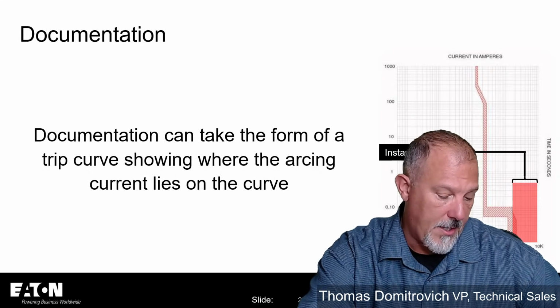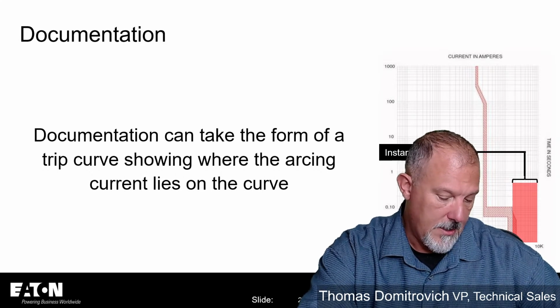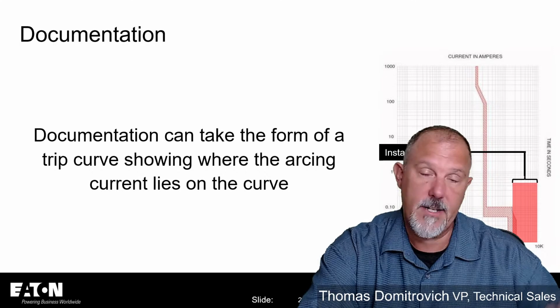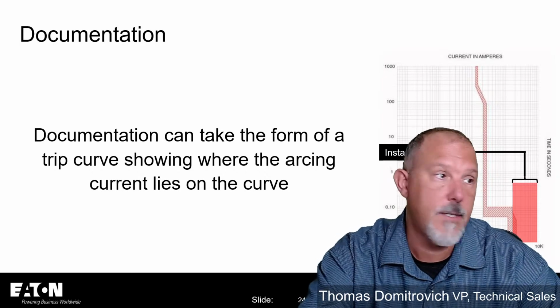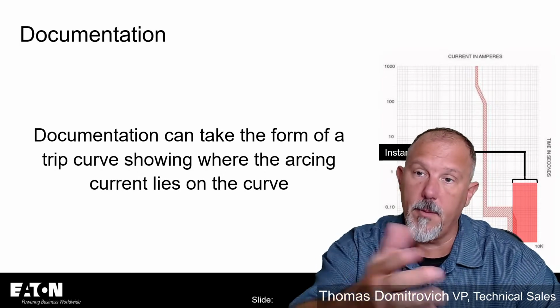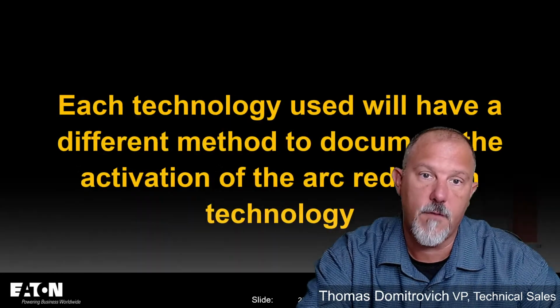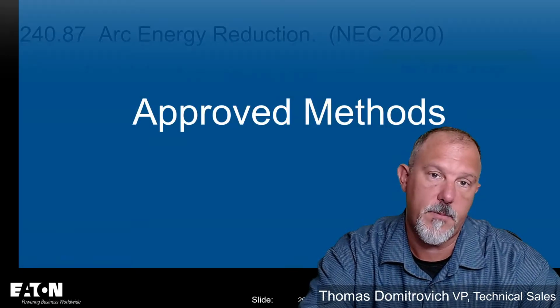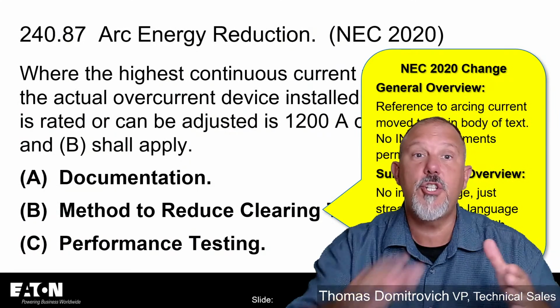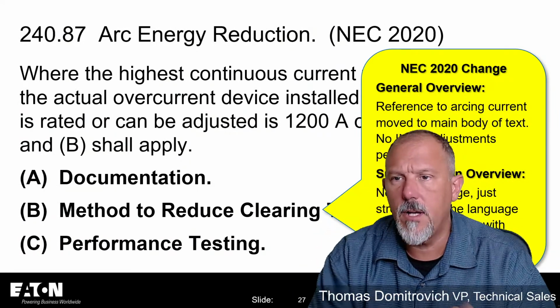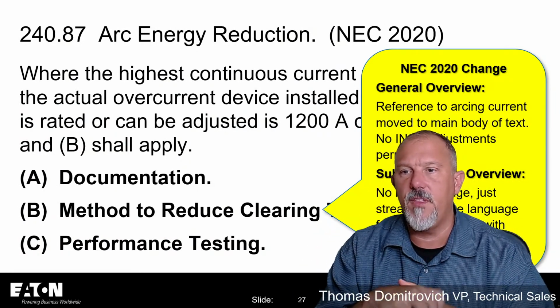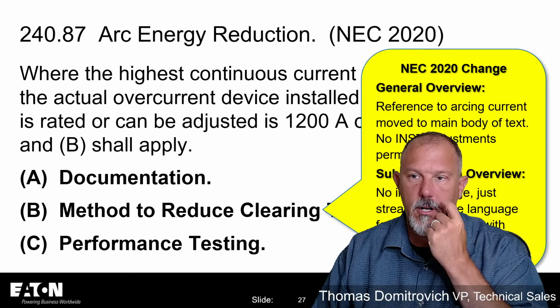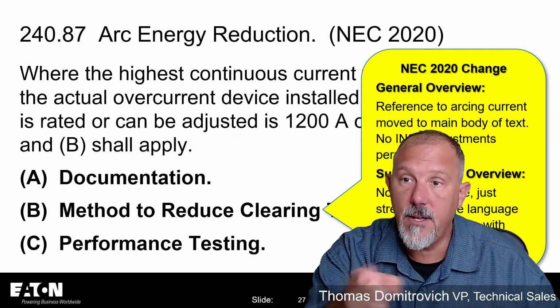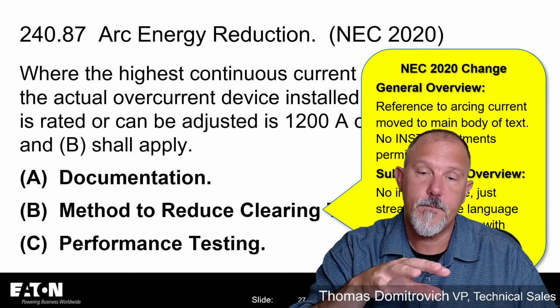But there's nothing in here that says that it has to be a qualified individual. So anybody can do that. I would argue you'd probably want to look for their capabilities. And then once you have said, okay, so would the arc flash label be with the arc reduction, before arc reduction, or both? I'll tell you what they do, Chris.